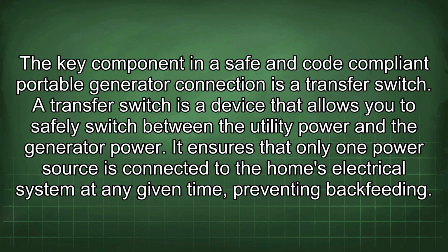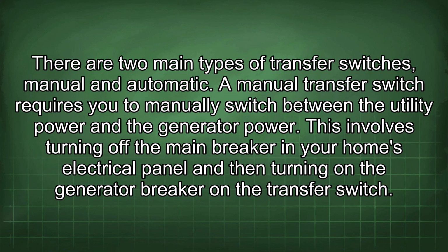The key component in a safe and code-compliant portable generator connection is a transfer switch. A transfer switch is a device that allows you to safely switch between the utility power and the generator power. It ensures that only one power source is connected to the home's electrical system at any given time, preventing backfeeding. There are two main types of transfer switches, manual and automatic.